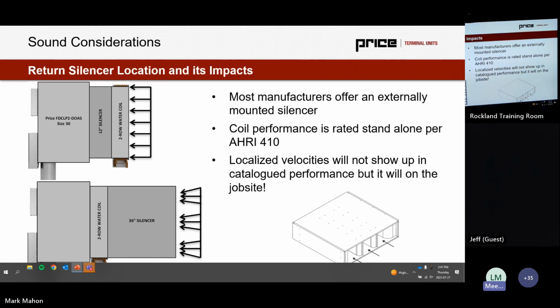So we tested our silencer in both configurations, upstream and downstream of the coil, and we found that it could have up to an 8% difference in capacity. But because of the way these products are certified and cataloged, it won't show up on a catalog page. So we chose the version that is better for performance, more expensive for us to ship. We obviously still have to compete with market competition, so we trade off margin for capacity, but that's a worthwhile cost because we want to make sure our products actually work and do what they say they will.